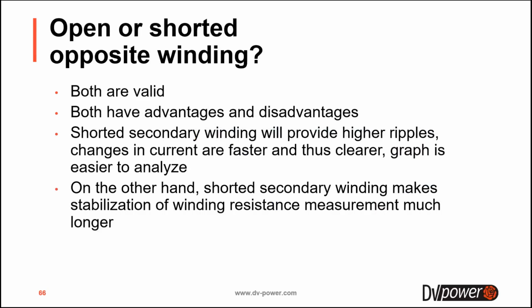And another dilemma is whether you should record the DV test when the opposite windings are open or shorted. Both ways are valid, and both of them have advantages and disadvantages. The benefit of having a shorted secondary or opposite winding, so if the tap changer is on the primary and you short the secondary winding, is that you will get higher ripples. So the changes in current will be faster and more clear, and it will be easier to analyze the graph. But the disadvantage is that if you short the secondary and do winding resistance on the primary side, the stabilization of the winding resistance on the primary side will take much longer. So you will get a clearer graph, but you will prolong your measurement.